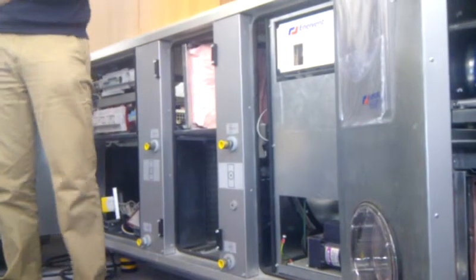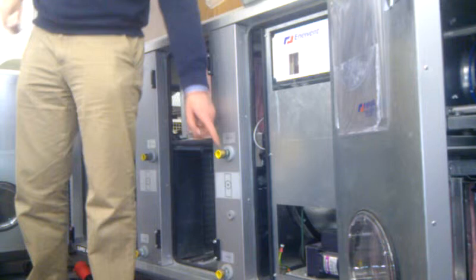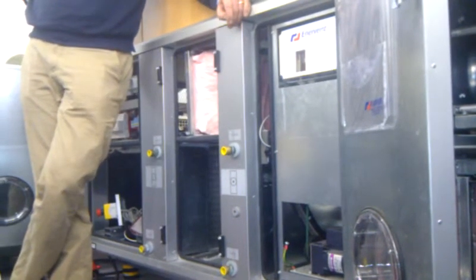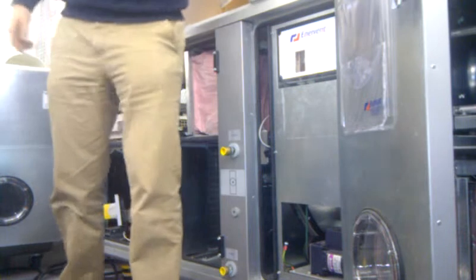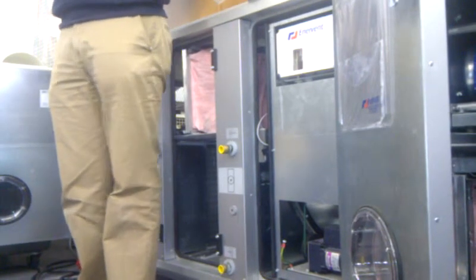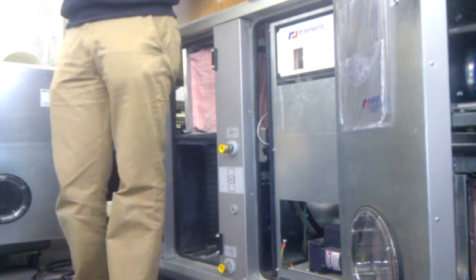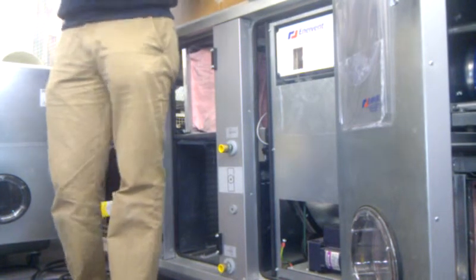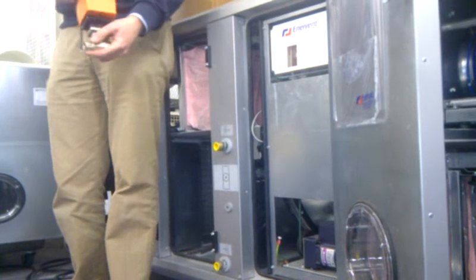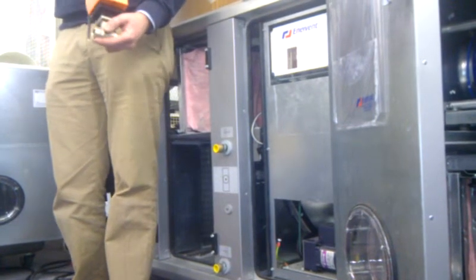Whatever's supplying that with heat, for example, the boiler. Is that hooked up to the boiler? How is that telling us to bring in water? There's the valve. No, the water is set to always have a flow temperature of 70 degrees. That's like the boiler you have at home. So that's always putting out the water at the standard temperature. The only thing that happens then is that the valve, either 2-port or 3-port, opens or closes to take the water when it needs it.